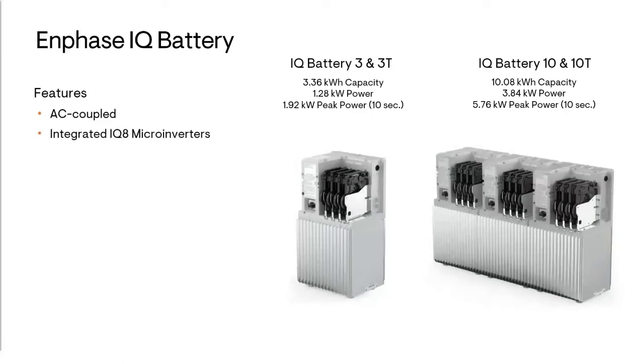Each IQ Battery has multiple integrated IQ8 microinverters. This provides redundancy and improves reliability compared to systems with a single inverter. They're also field serviceable, so in the off chance of a single microinverter failure, you can easily replace that one microinverter with a new one instead of taking down the whole battery and shipping it back to Enphase.